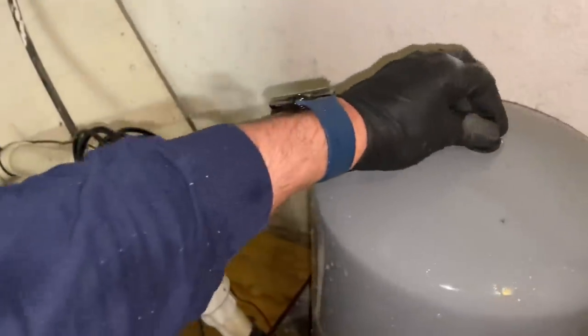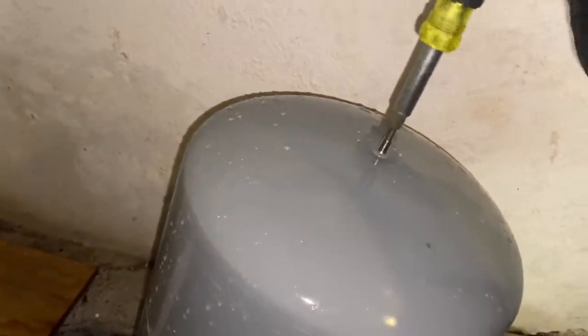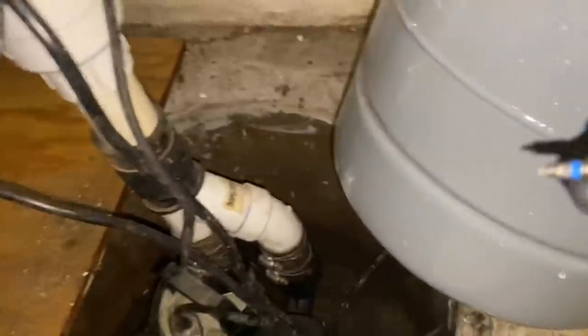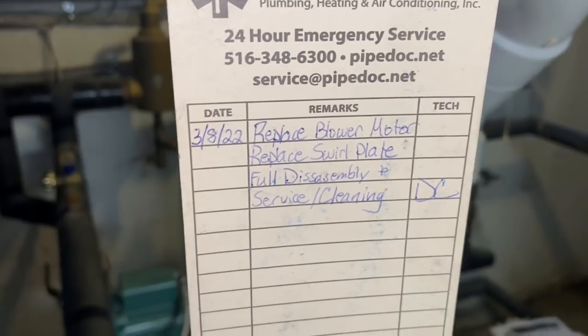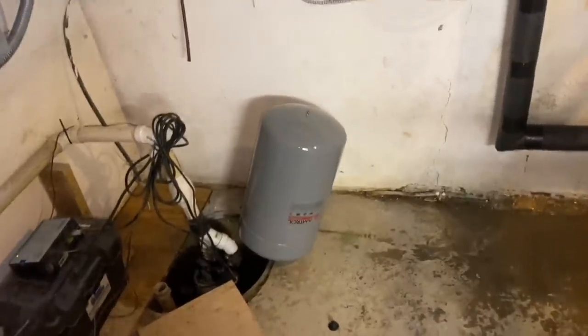Tech tip on how to deal with expansion tanks so you don't get water all over your truck. You could cap off the port, but since he's already draining into a source, he removes the Schrader core using a Klein 11-in-1 tool which has the Schrader core removal feature. He notes Daniel was here on March 8th - about four weeks later they're back because the relief valve is dripping due to the failed expansion tank.